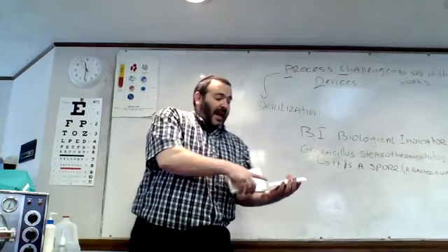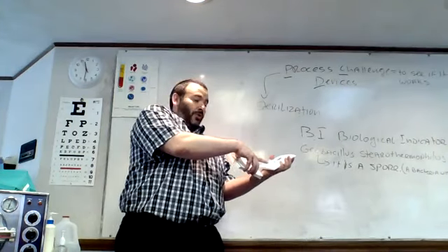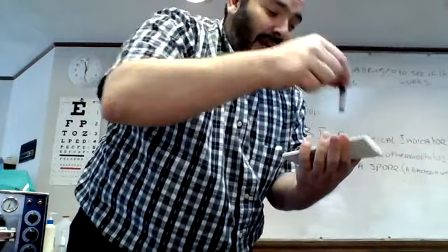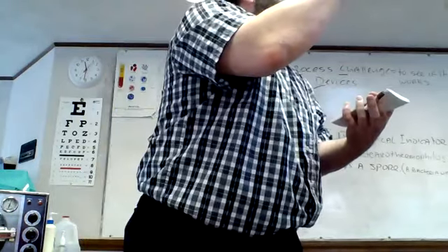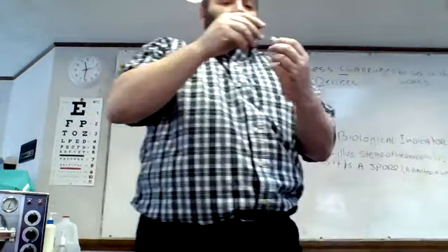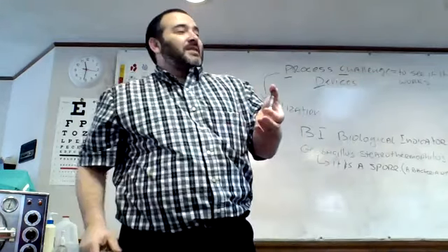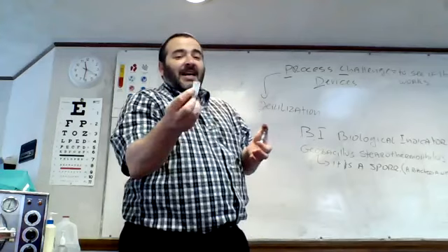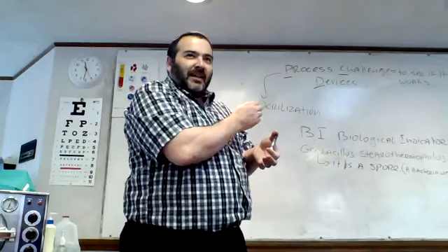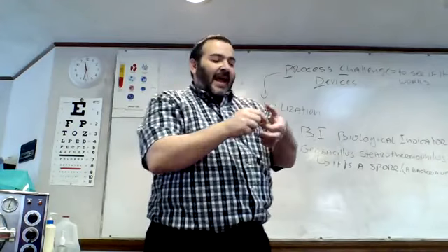All right? We have an ampule, and I take it out. It's wrapped in a here for you to see. And inside here, we also have something else. Inside this ampule, I don't want to open that up, is the spore of Geobacillus stearothermophilus. And in here, just to be safe, it's also a chemical indicator. We haven't put that on the board yet, so we have a chemical indicator and a biological indicator.